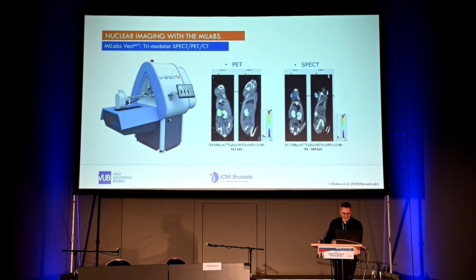It's a tri-modular system: SPECT/PET/CT. The PET mode is not a ring-based system as traditional PET systems, but collimator-based, while still offering the possibility to image 511 keV photons. We can always switch out PET isotopes for SPECT isotopes — here we see a comparison between gallium-68 and gallium-67.